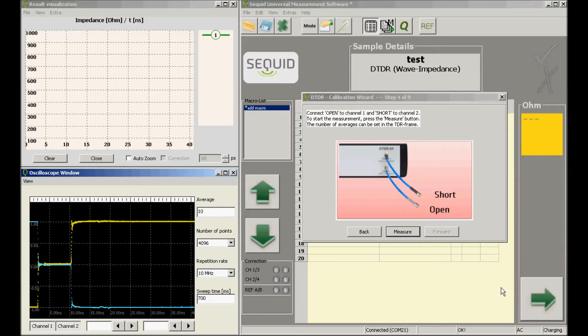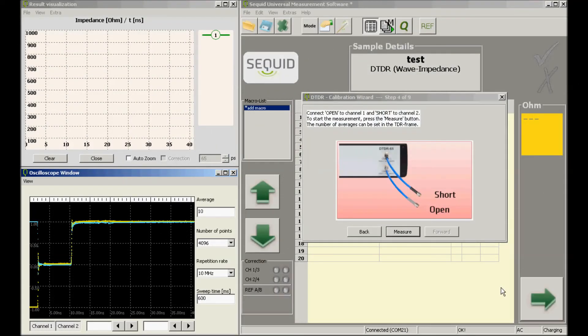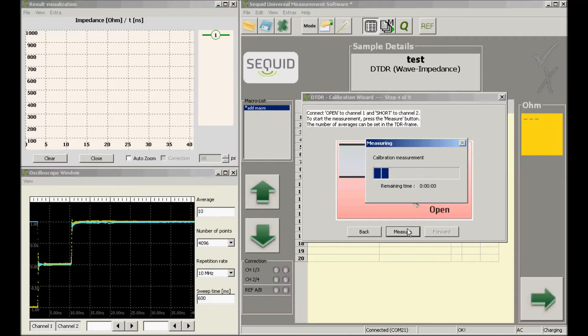We are now starting our first calibration measurement. As you can see, the yellow curve — which is channel 1 — is reflected in the same direction as the incident step because the termination is the open standard. The blue curve is channel 2, terminated with a short.